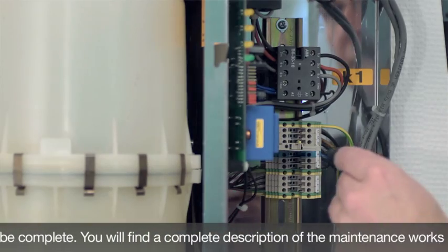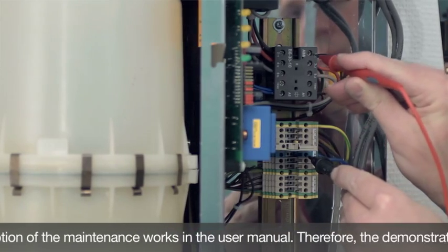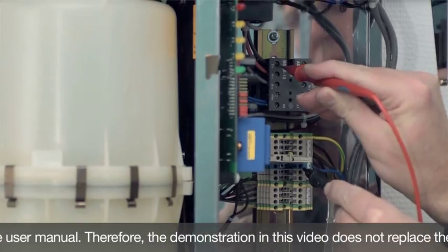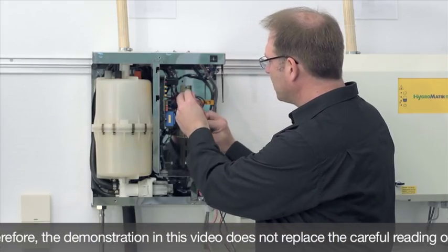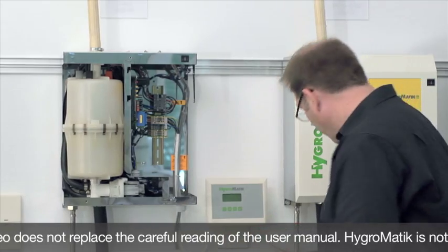Although we had disconnected the power supply earlier, I will check again anyway that no voltage is in fact applied to the unit. That means I will take measurements again at all points of the main contactor. There is no voltage applied, so I can be reassured and work in the left area.